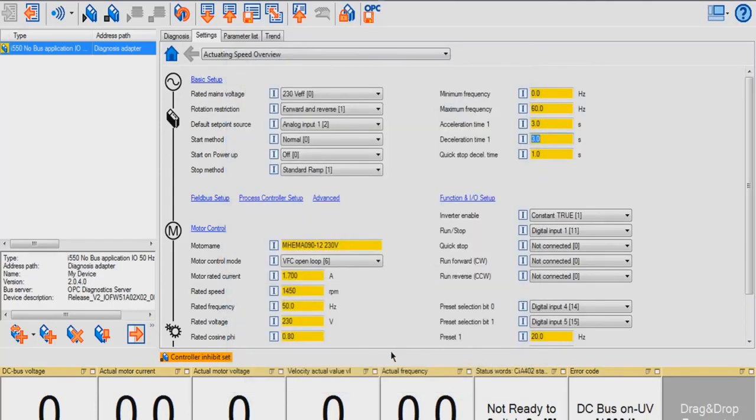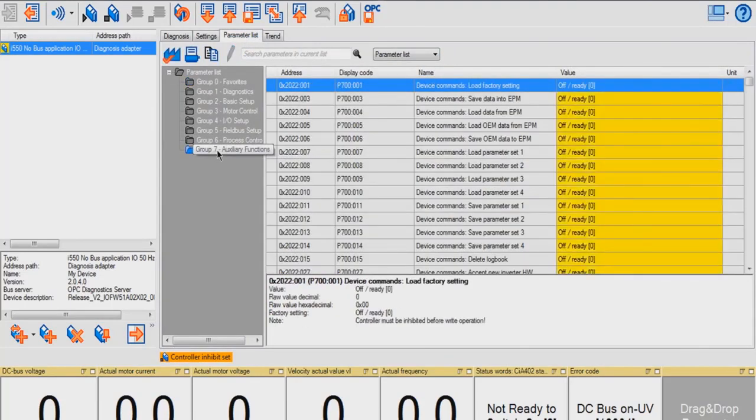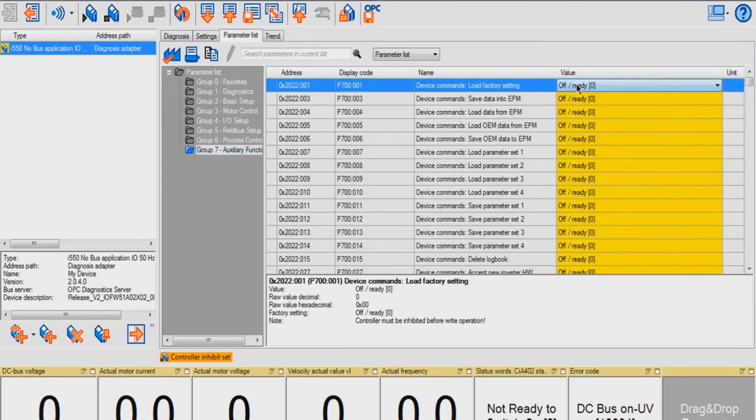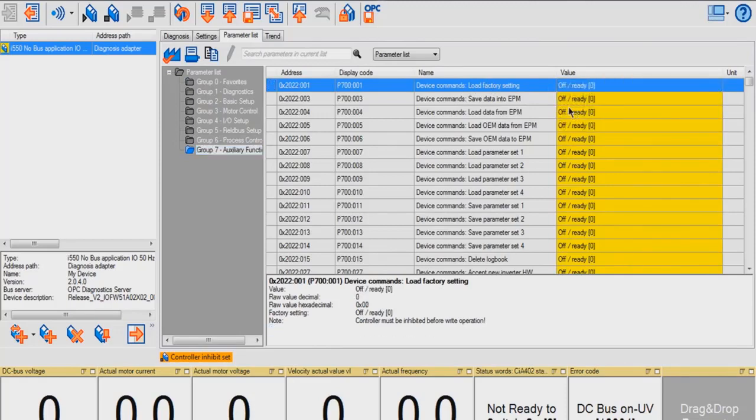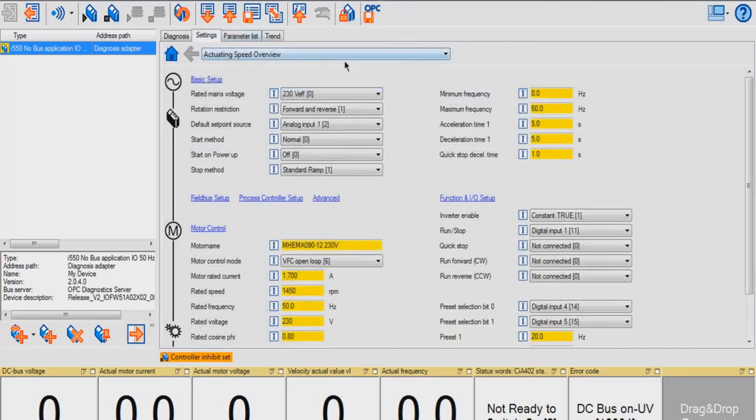Now, I'm going to be changing the device settings back to defaults. To do that, go into the Parameter List tab, go to Group 7 Auxiliary Functions, and in Load Factory Setting, change this to On Start. Go back to your Settings page. As you can see, the parameters are set back to default.